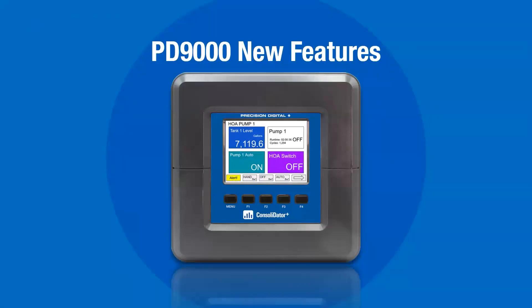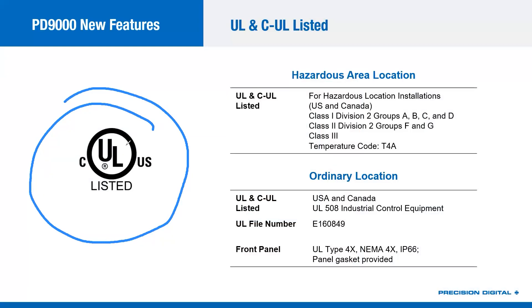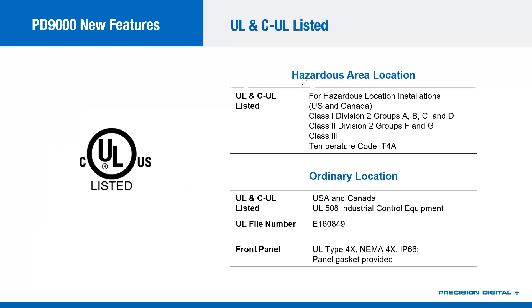Let's dive into the new features on the Consolidator Plus. Beginning with UL and CUL listing — you will now see this UL mark on the side and on the label. It means the product is both U.S. and Canadian listed: UL for Underwriters Laboratories and CUL for the Canadian version. It is UL listed for both hazardous area locations, carrying Class 1 Div 2 approvals, and for ordinary locations under UL 508.